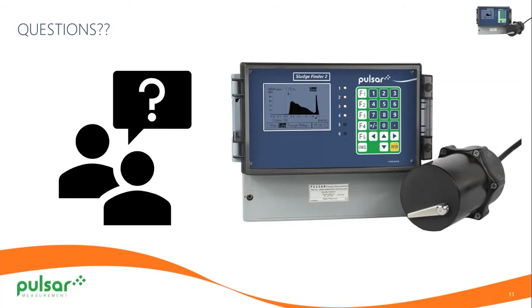Any more questions? I have, can you discuss the density measurement, please? The Viper sensor is looking for the settlement layer with the density with the meter. So you have a clear liquid, and within that you may have some floating particulate. As that particulate settles out, you will create a density level, and the meter will pick up, and the ultrasonic wave will come off of the density level as it builds up, giving you the measurement.